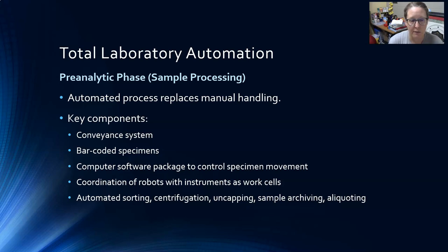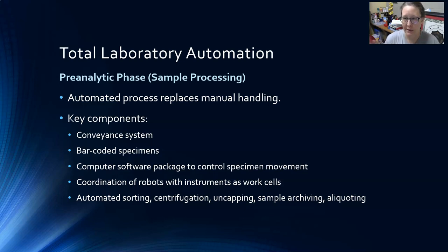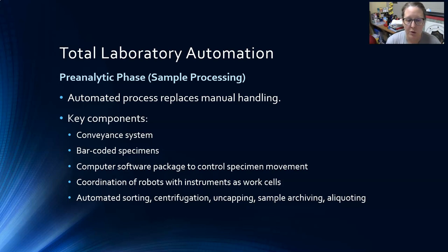Key components of automation in the pre-analytic phase include a conveyance system — something like a conveyor belt to transport tubes across the lab to different areas. Barcodes are needed to track tubes through the system, along with computer software to control specimen movement, direct which track to put it on, and which analyzer to send it to. Robots are coordinated with instruments as work cells, and there is automated sorting of specimens — you can load all kinds of tubes and the system sorts between hematology, chemistry, coagulation, and specialized immunoassay chemistry testing.